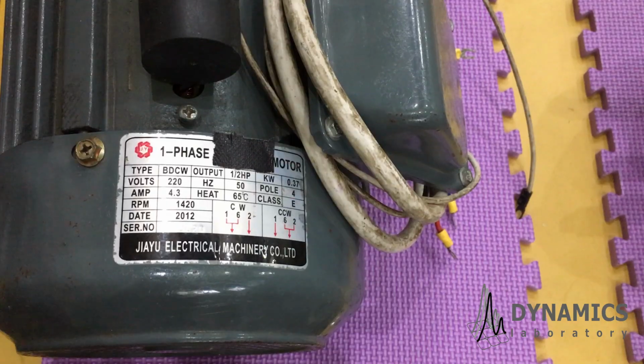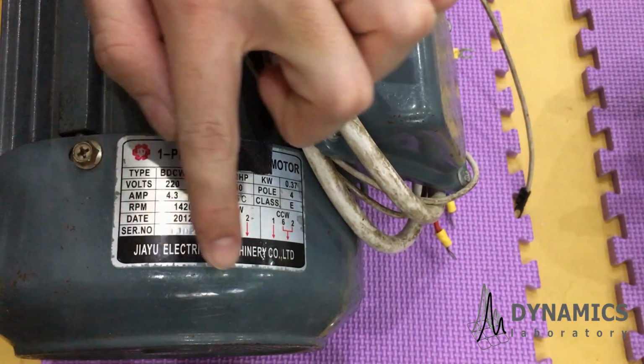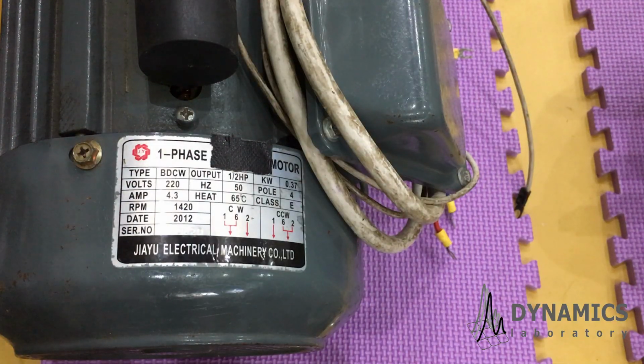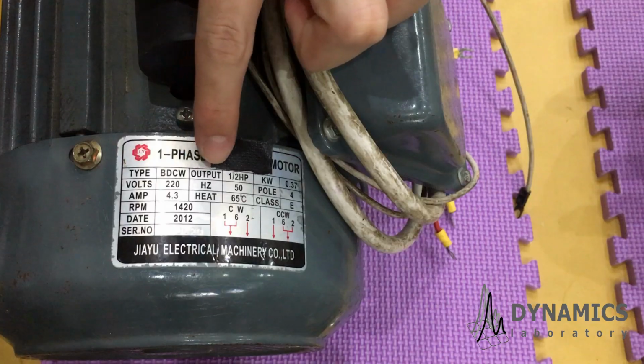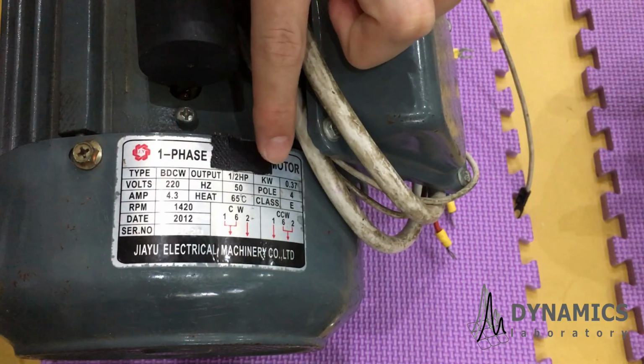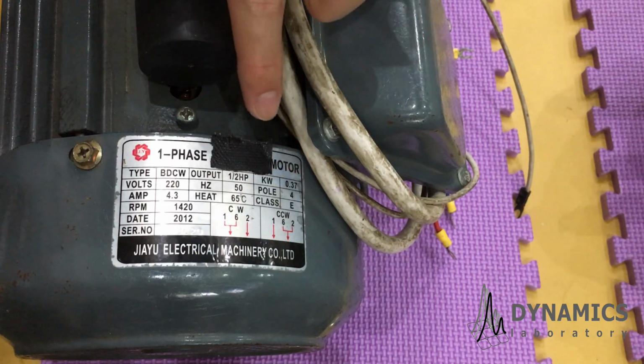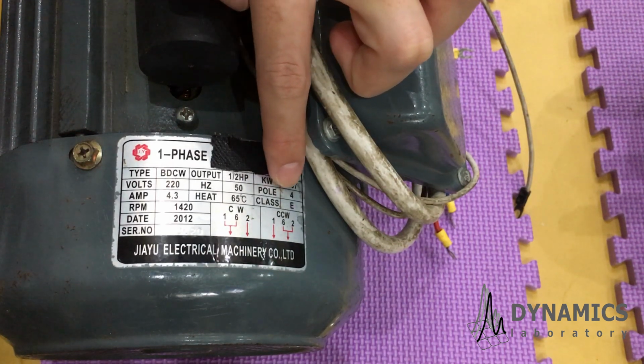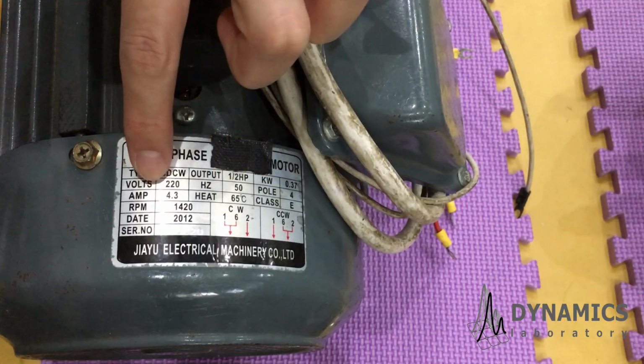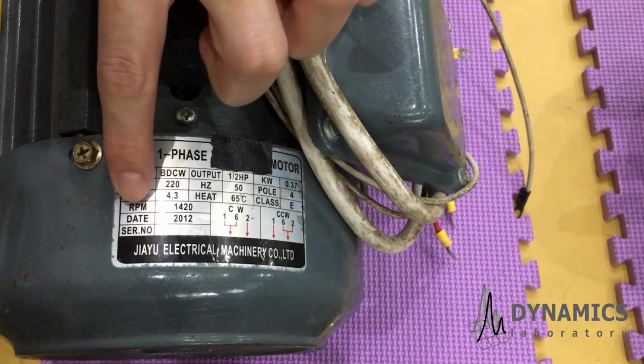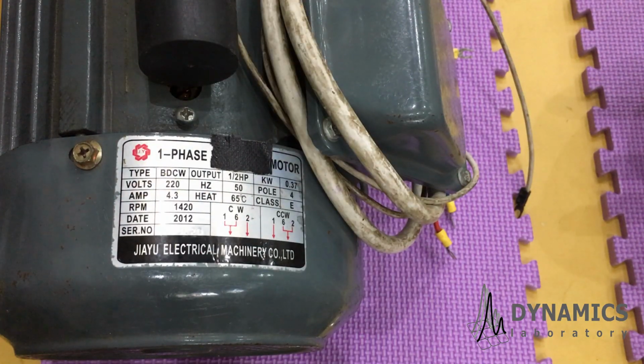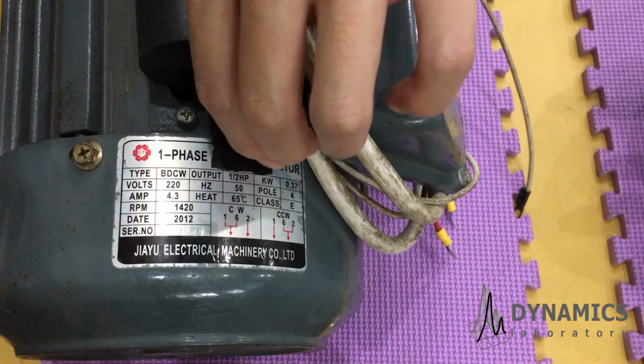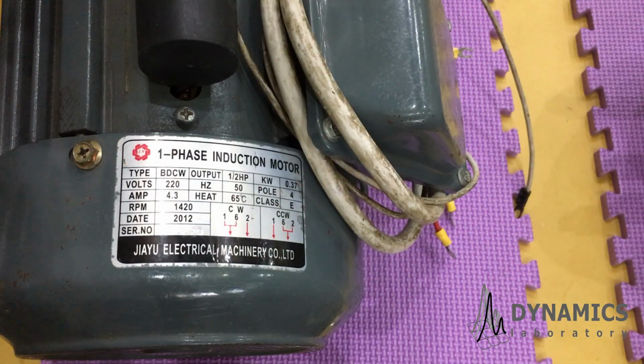Move to the one-phase AC motor name tag. You can see in here, we have several pieces of information. Start from the output power, 0.5 horsepower or in kilowatt units. And then you have how many poles are in this AC motor, the frequency, the voltage, the ampere, and also the RPM or the rotational speed. Based on the RPM, you know that this is an AC induction motor, right? Yeah, that's right. That's why when you open this, the motor name tag also shows you one-phase induction motor.